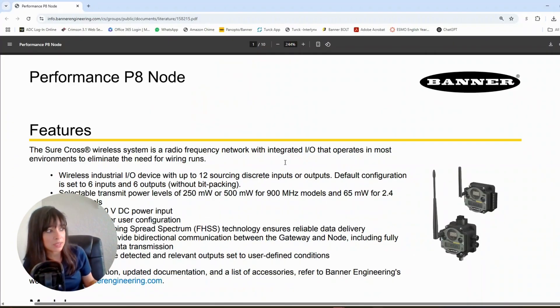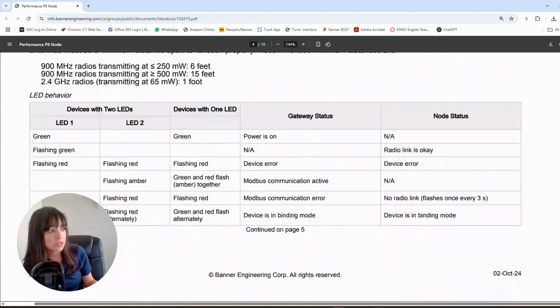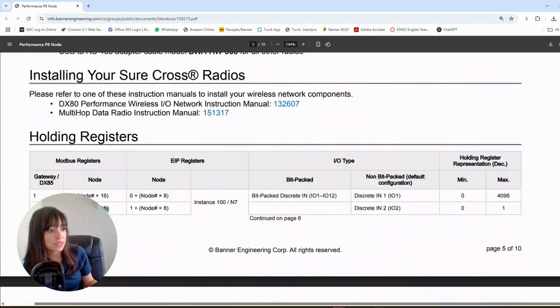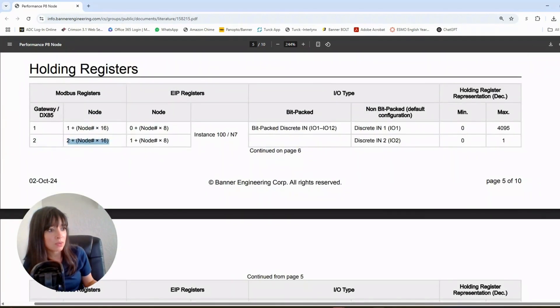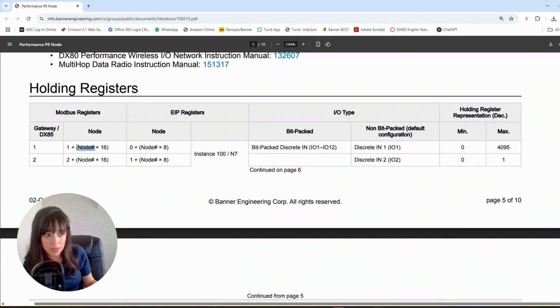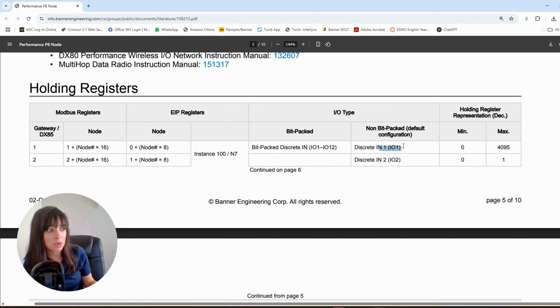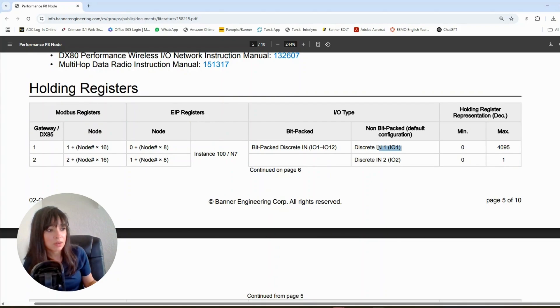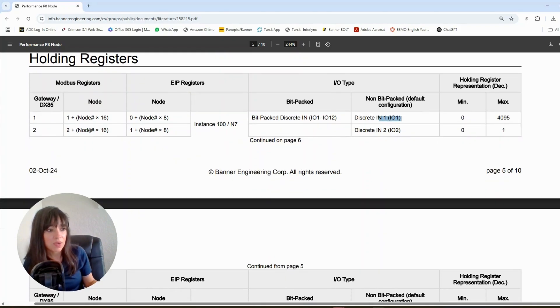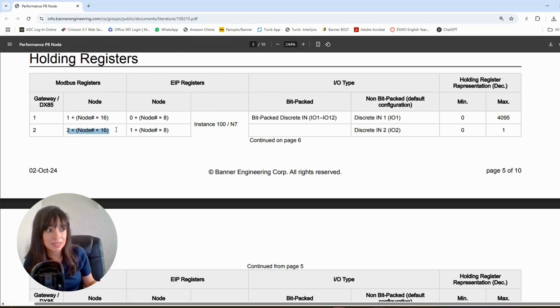I know everybody likes to read the data sheet, so we're going to scroll all the way down to the part where we get to the holding register table. We notice that there is a formula, and if you are at node 1 like me, for example, times 16 plus 1, then that means that my holding register is going to start at 17 for input 1. Okay, if I'm on input 2 of node 1, then that puts me at holding register 18.